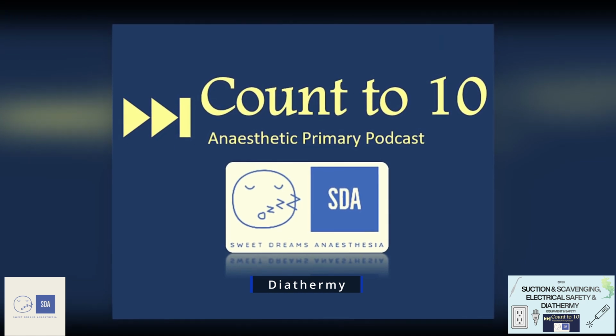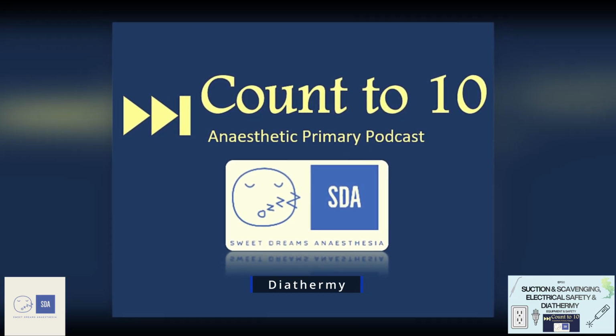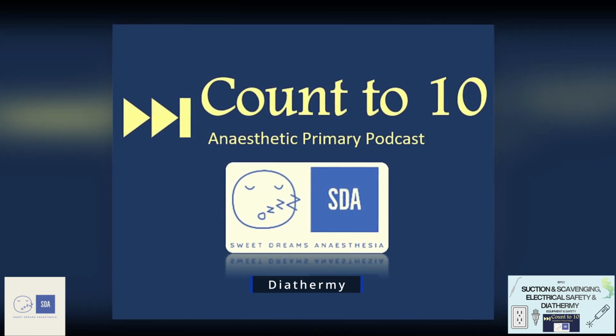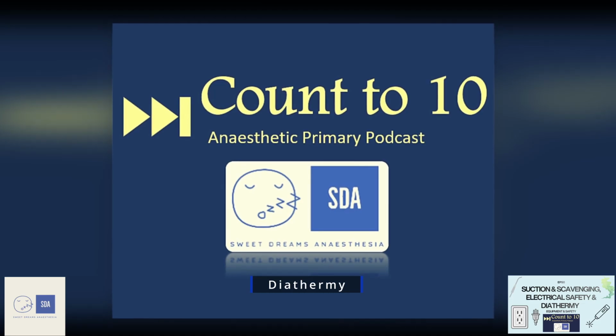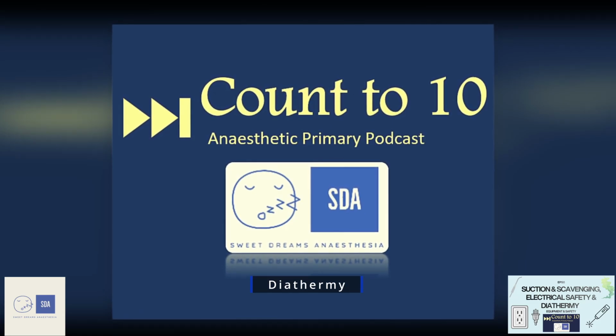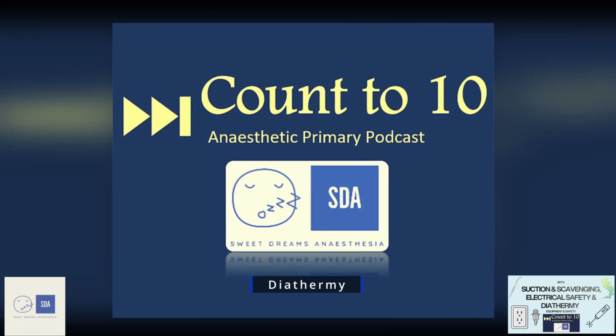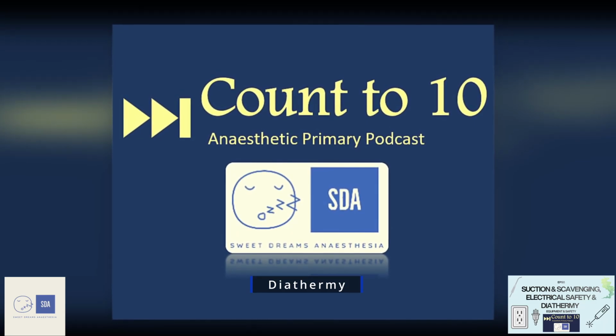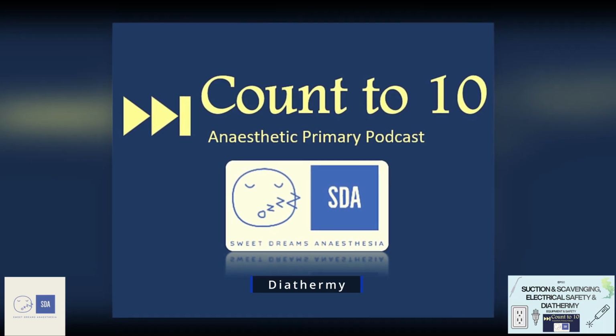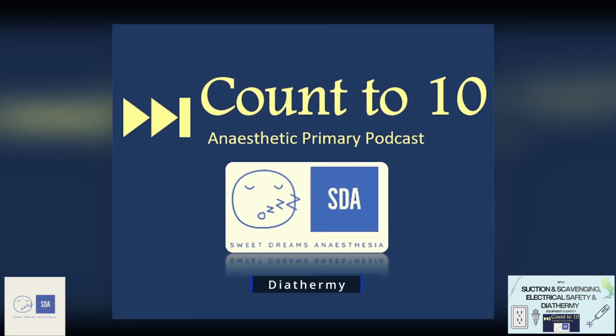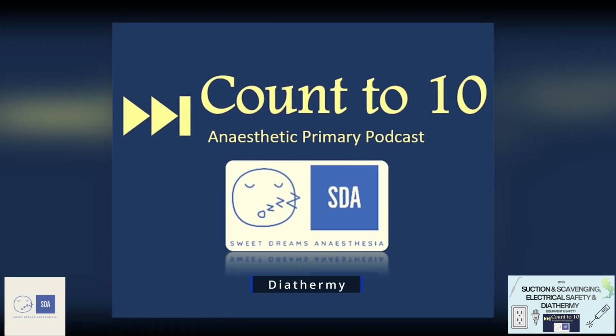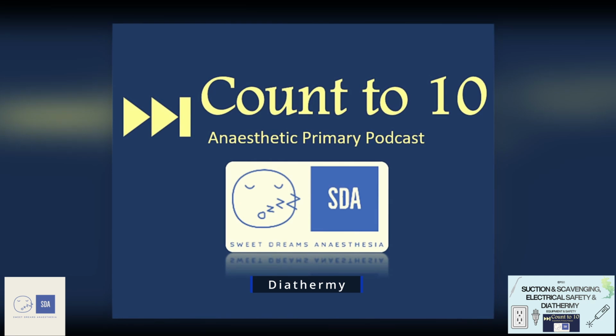Other risks are simple things like it needs to be used by trained professionals. When it's being used and burning tissue, that tissue is creating smoke, which can be potentially carcinogenic to the people around it. The other main risk we especially get worried about is diathermy use in the presence of internal cardiac devices, specifically pacemakers and defibs, because diathermy can alter what those devices sense and can lead to an inadvertent shock or a change in rhythm. For this, we typically recommend to avoid diathermy use within 15 centimeters of the device location, and if this cannot be achieved, then we advise to use bipolar for the lowest duration possible, because bipolar is much safer than unipolar, because unipolar will pass its electrical current through the patient's body until it gets to the ground plate.